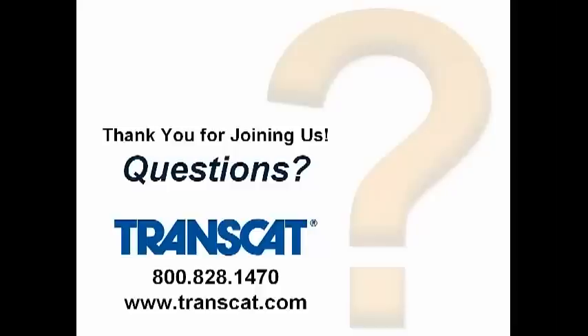So the PCS feature that we have in CalTrack for our technicians is there to allow them, when they have the uncertainties, to see where they are in that guard band region. And if they're in the guard band region at all, regardless of the TUR, that's when they'll make the adjustment. We do not optimize unless the customer asks us to optimize, meaning adjusting every time the instrument comes in, regardless of where it is. Again, that's a specific request.